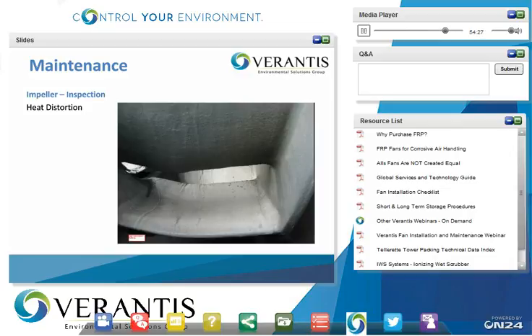Main causes for this would be your process temperatures. You could have a blocked mesh pad or mist eliminator in the duct system at some point, or you could potentially run the fans with the dampers closed. And I've seen this happen several times, so it will restrict the airflow. You won't have enough air running through the blower to keep it cool, and they will start to soften and grow.